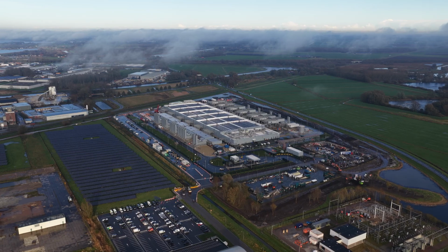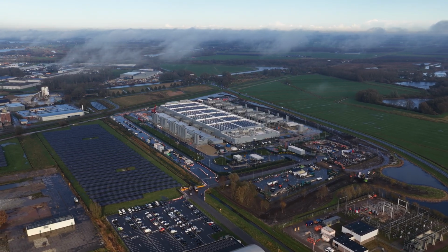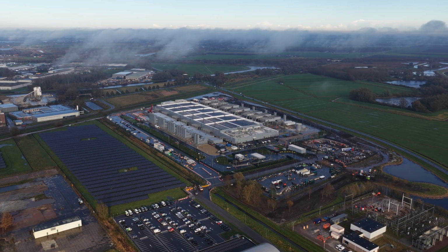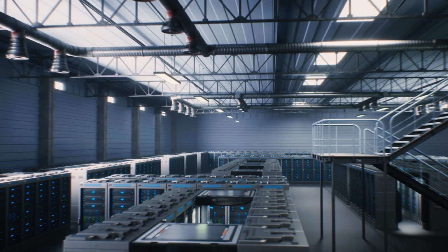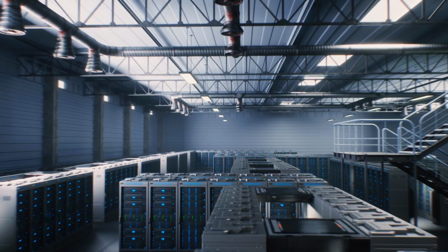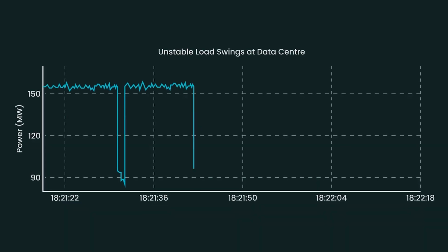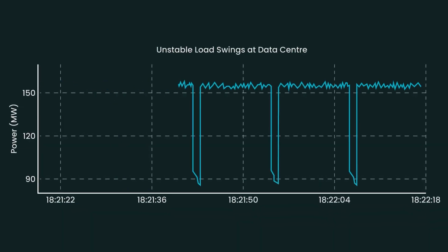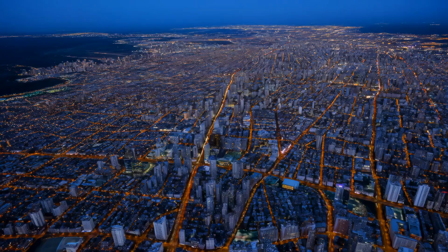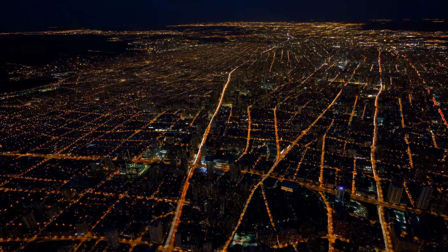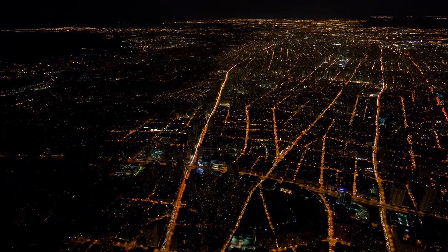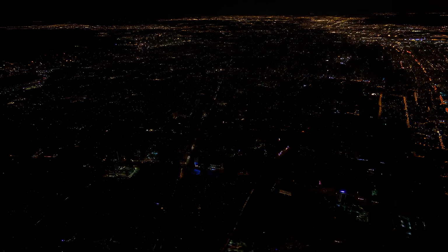AI data center power usage is staggering. They want 99.999% uptime and don't want to sacrifice compute for anything. When you talk gigawatt scale data center, 30 to 80% of the load swings multiple times per minute. A gigawatt, for reference, is about the equivalent of 1 million homes worth of power. At gigawatt scale, those loads are large enough to potentially cause a rolling blackout that could take out an entire grid.